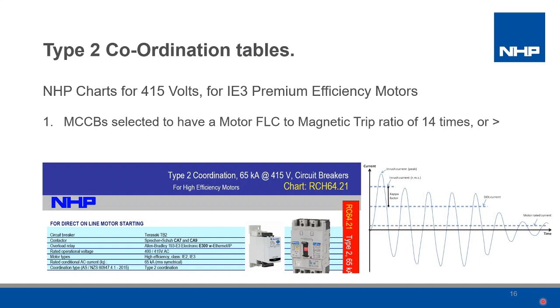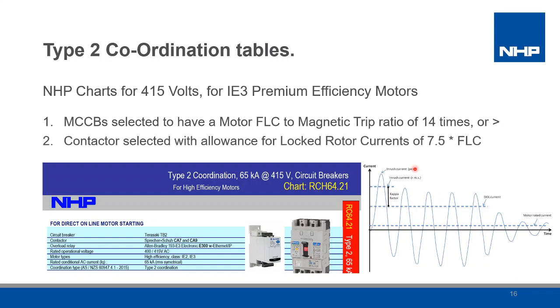The tables compiled have been formatted for premium efficiency motors to prevent nuisance tripping during start. This is due to the high inrush peaks, which can be up to 22 times the full load current. The starter trip multiple is based on the magnetic tolerance band at maximum setting. The contactors are sized from the MCCB requirement and also selected to suit higher locked rotor currents, with premium efficiency motors seeing up to 9 times full load current.